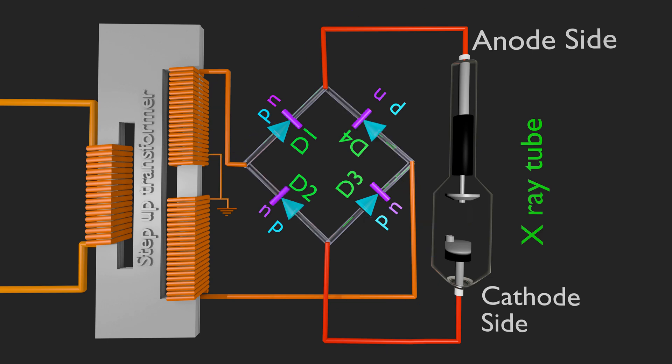Consider other half cycle of AC, upper pole of secondary winding at negative polarity in respect of lower side. Diode 1 will be reverse biased as negative polarity of it is connected to p side of D1. Hence, D1 cannot conduct here. Now D2 is in forward bias as negative polarity of it is connected to N side of D2. Cathode of X-ray tube will get negative polarity as it is connected through D2.